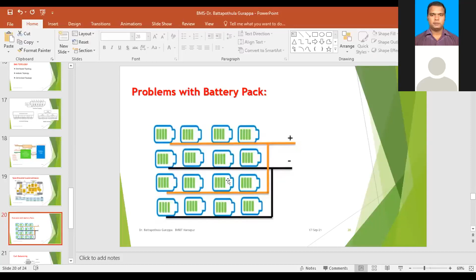It's not only because of the supply; maybe because of these connections a small voltage difference appears. But due to the internal resistance of each cell, there is a large voltage difference. This is very dangerous for the battery, because that imbalance causes more circulating current. Then the temperature at different places of the battery pack becomes very high, and definitely thermal runaway is going to happen.